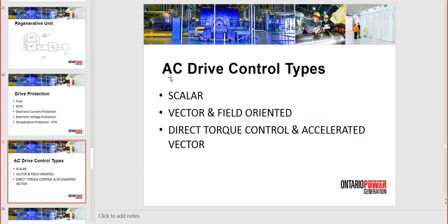with this slide we start talking about the control. If we have three types of drives for the power side, we also have three types of control. So the control can be scalar, simply volt per hertz, easy to set up, usually open loop. It can be closed loop and get better performance, but really you don't need to tune any regulator or do anything, just adjust boost, how much voltage you want when it's starting, auto boost, how much of the current you need to set up as a feedback from the load. So the higher the load, the higher the auto boost will help the motor to develop more torque.